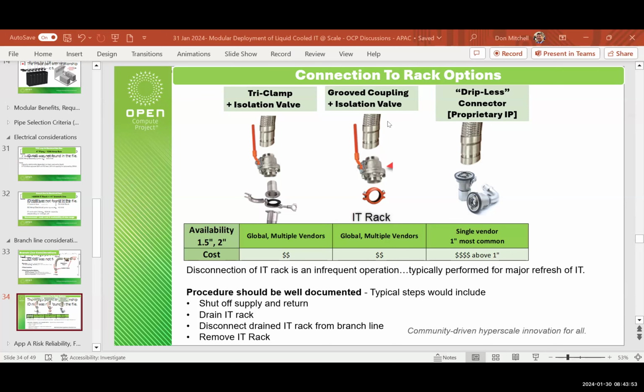I generally think that no matter how dripless people say it is, if it's over an IT rack or over an alarm sensor, this is one area I'd encourage IT vendors to address: come up with an MOP or SOP that actually covers how we connect and disconnect these IT racks every 3 years or whenever we pull them back for maintenance.